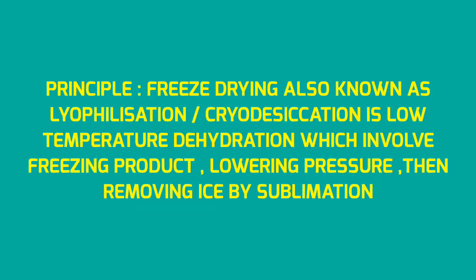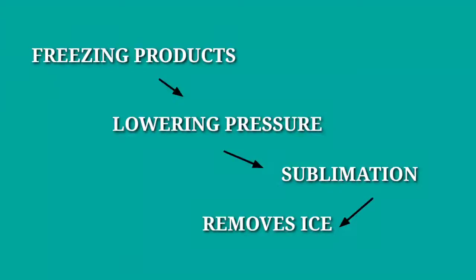The principle involved in the lyophilizer is freeze drying, or cryodesiccation, also known as lyophilization, which is a low temperature dehydration process. It generally involves freezing the product, lowering the pressure, then removing ice by sublimation — that is, converting solid directly to vapor without converting into liquid — and finally removing the ice so that a dry powder is formed.